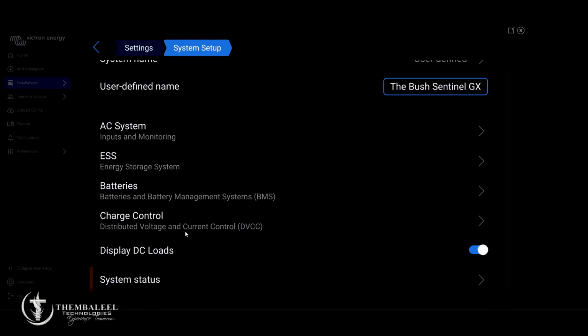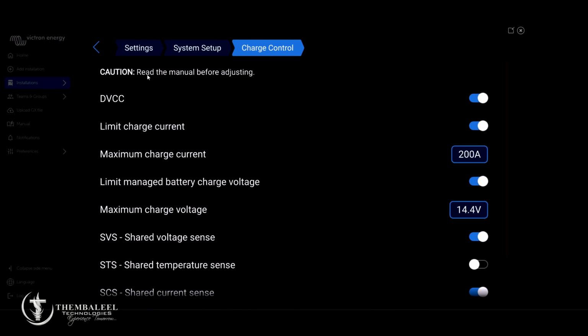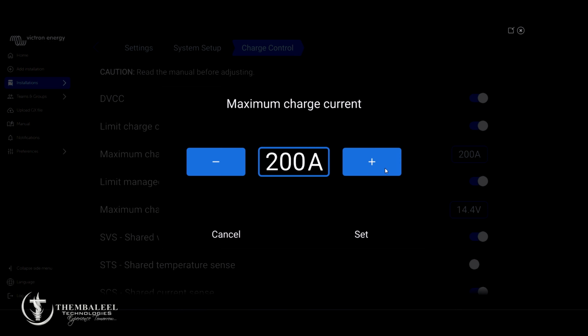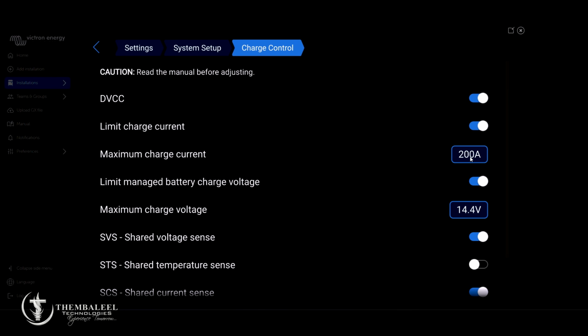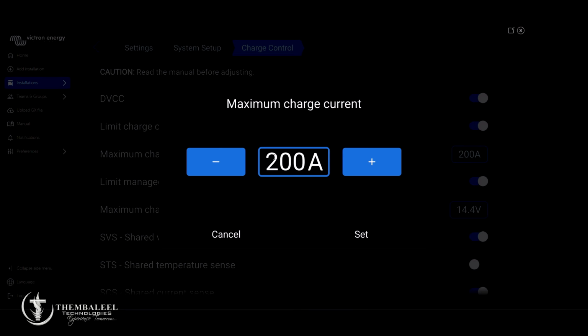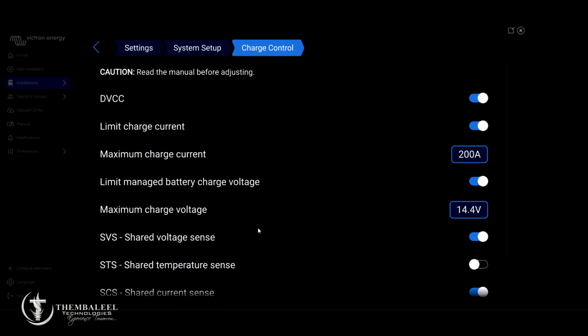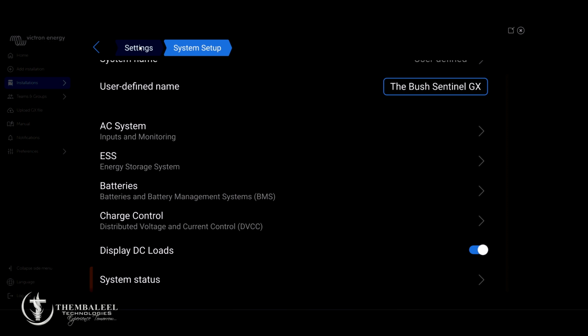One other thing that's very important: when you go to your DVCC, you can decide how much current your system is able to tolerate. In this case, I put 200 amps because the battery can handle that. But if you drop this to 50 amps, no matter how much sun or how much grid is available, the system cannot pass that threshold.